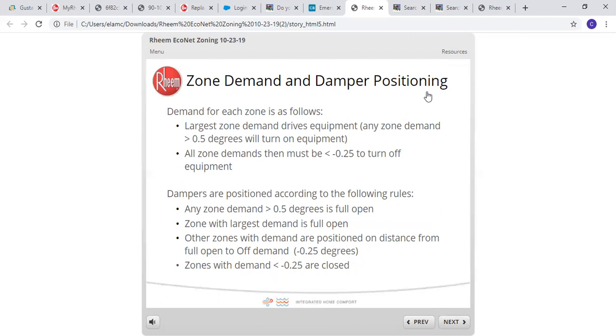You have your zone demand and damper positioning. Demand for each zone is as follows. Largest zone demand drives the equipment. Any zone demand greater than or less than 0.5 degrees will turn on the equipment. All zone demands then must be greater than or less than 0.25 to turn off equipment. And then the dampers are positioned according to the following rules. Any zone demand greater than or less than 0.5 degrees is fully open. The zone with largest demand will be fully open. All other zones with demand are positioned based on distance from full open to off demand 0.25 degrees. The zones with demand are 0.25 closed.